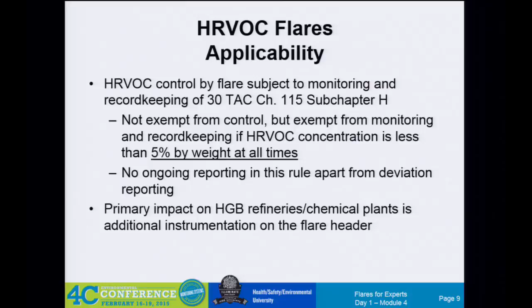So the continuous data is used for hourly emissions. They have to calculate the minimum heating value and the exit velocity all the time. It really changed from, instead of doing that one-time performance test for 60.18, now you're needing to show compliance with this on an ongoing basis. So that was something new for people.